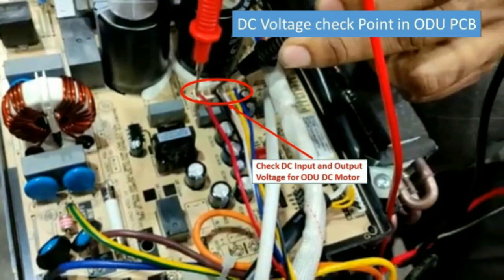And the ODU fan motor can be AC or it can be a DC fan motor. If it is a DC fan motor, we have to measure the DC voltages between the points of the ODU fan motor. Input voltage should be more than 320 volts and output voltage should be 14 volt DC.